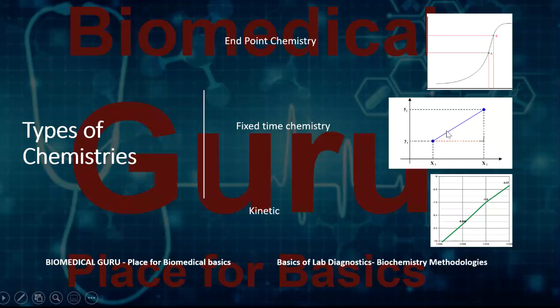Next comes the fixed time chemistry, where we measure how much color is developed in a particular period of time, typically between 1 minute and 2 minutes. If more color is developed during this time, that means there is more concentration. If less color is developed during this time, that means there is lesser concentration.